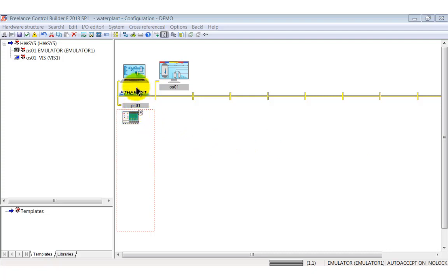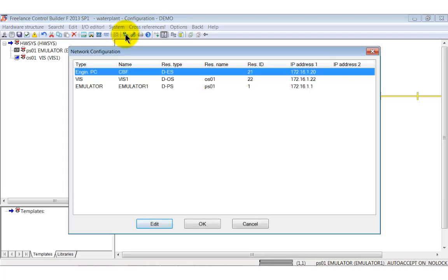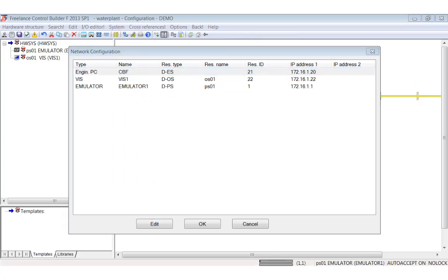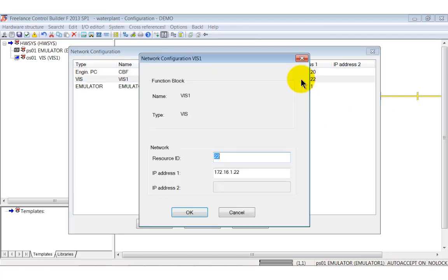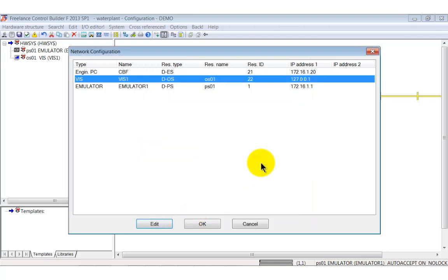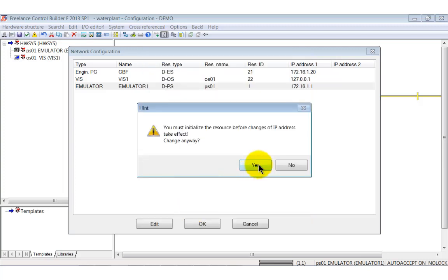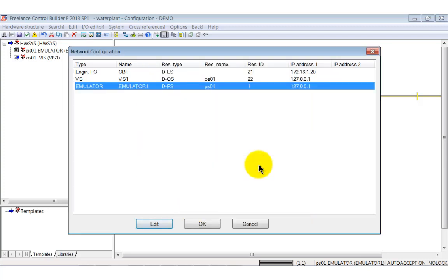Function block diagrams are working in the same way with both controllers, the real AC800F and the controller emulator. Now we have to adjust the IP addresses for the emulator and DigiVis operator station. Therefore, open the network configuration window, selecting network in the hardware structure menu. Edit the resource ID of the operator station and its IP address. Copy the IP address into the clipboard before leaving the dialog. Perform the same step with the emulator and paste the IP address here.